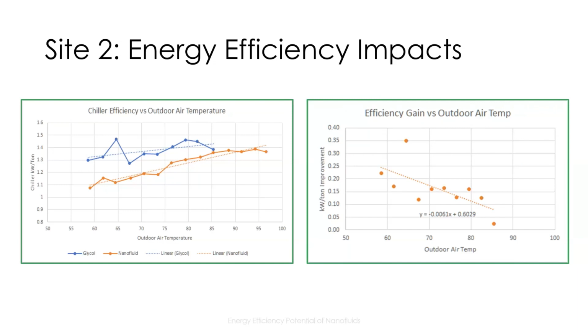The chiller's cooling capacity is about 100 tons at full load with a rated efficiency of about 1.2 kW per ton. The meter data shows the chiller efficiency closer to 1.4, but the low loading on the chiller is likely the primary cause of this issue. The right-hand graph's trend shows a more significant efficiency increase at lower outdoor air temperatures and loads than in the peak loading conditions.